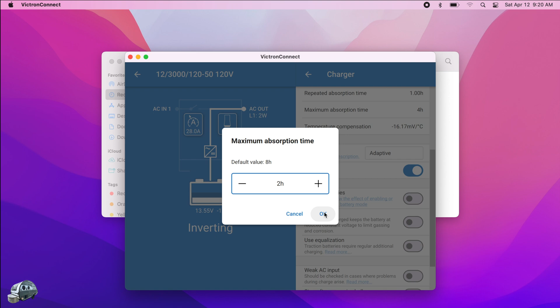Change the absorption voltage to 14.6 volts. Next, change the float voltage to 13.6 volts. The maximum absorption time for us is 2 hours. Change the charge curve to fixed. Turn lithium batteries on. And that is it for the Multiplus. All of our factory Victron gear is now fully configured.